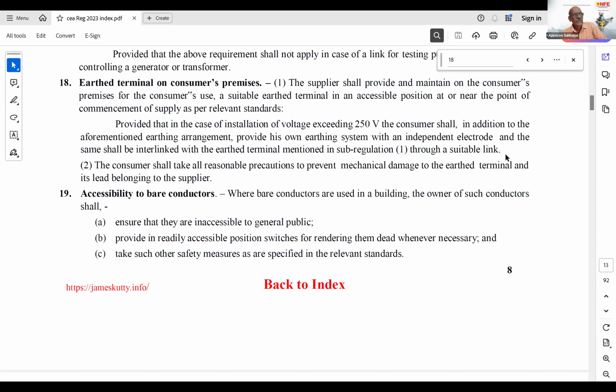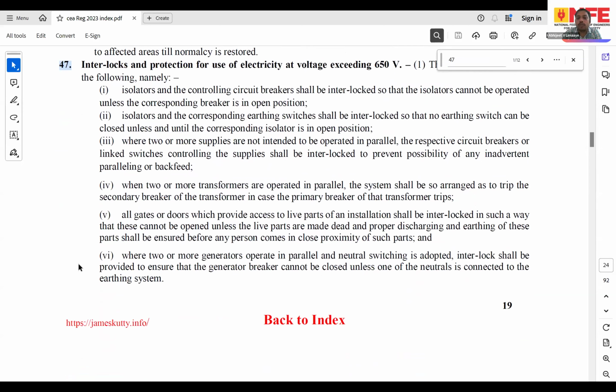Yes, sir. Thank you. So when it comes to diesel generators, typically when we are talking about synchronization, we'll be talking about two generators or more. The problem will rarely be there if you have one generator. If you have one generator and one transformer, the matter is quite simple. You have a four-pole breaker at the transformer end, you have a four-pole breaker at the DG end, and you can have the neutral in place when the DG is turned on.